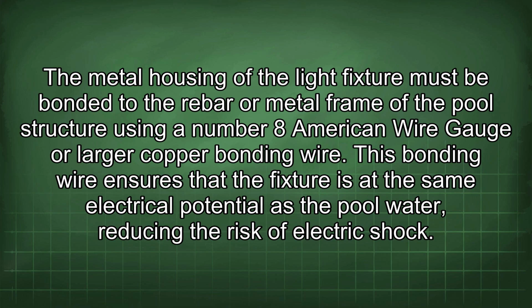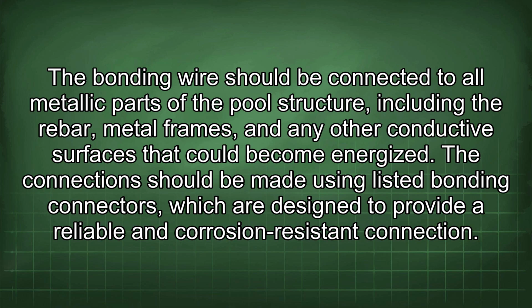This bonding wire ensures that the fixture is at the same electrical potential as the pool water, reducing the risk of electric shock. The bonding wire should be connected to all metallic parts of the pool structure, including the rebar, metal frames, and any other conductive surfaces that could become energized. The connection should be made using listed bonding connectors, which are designed to provide a reliable and corrosion-resistant connection.